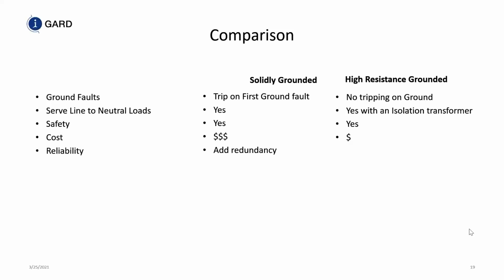And believe me, this is a feature that we've learned because we have some products that are considered extremely safe products. So they have a safety integrity level of 3 or higher. Adding more components to increase the reliability does not increase the safety integrity level. You have to ensure that the right components are in, not more components that can fail. So if you have a data center, you can actually put in a 2N+2 or an N+1, but that's adding redundancy. It's not adding reliability.